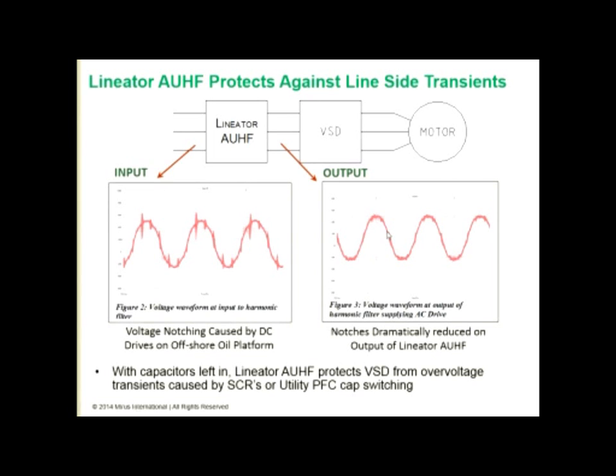So on the output of the filter, supplying the variable speed drive, we've reduced the overvoltage peak, and we've filtered out the ringing to produce a much cleaner sine wave to the drive, and this will protect the drives. But if we switch out the capacitors under lightly loaded conditions, this protection no longer applies. You lose this added protection.